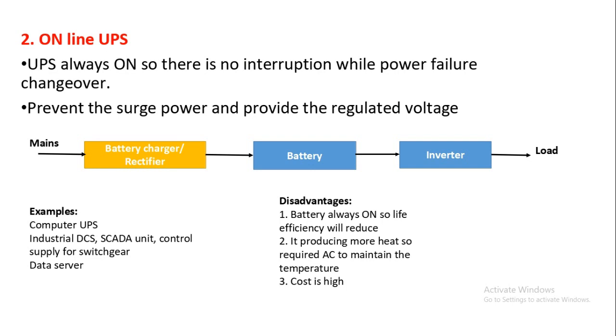The disadvantages of online UPS: since the battery is always on, its life efficiency will reduce. The load is always connected through the UPS, so the battery and UPS system are always on, meaning continuous charging and discharging happens, which reduces battery efficiency and lifetime. It also produces heat, so it requires an air conditioner to maintain room temperature at 20 to 25 degrees Celsius for the UPS to perform efficiently. The third disadvantage is that this type of UPS has a very high cost compared to offline UPS.